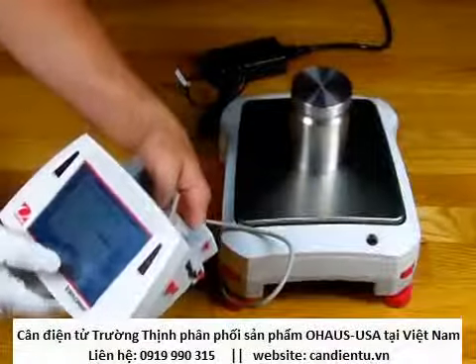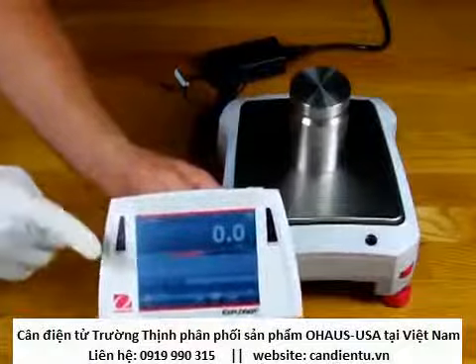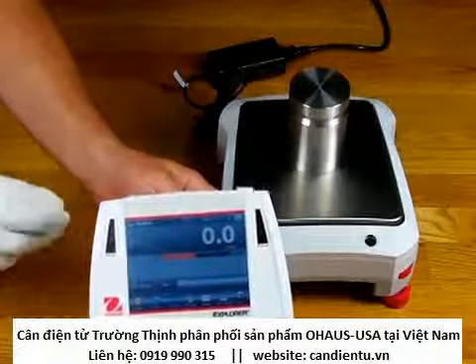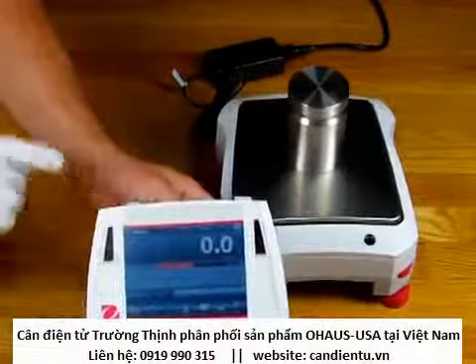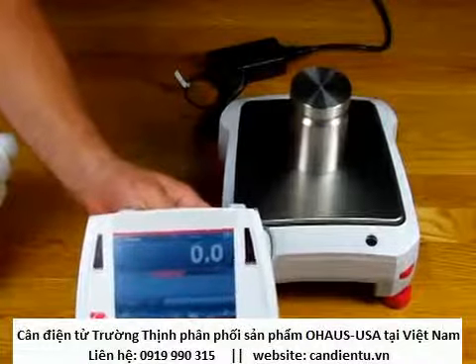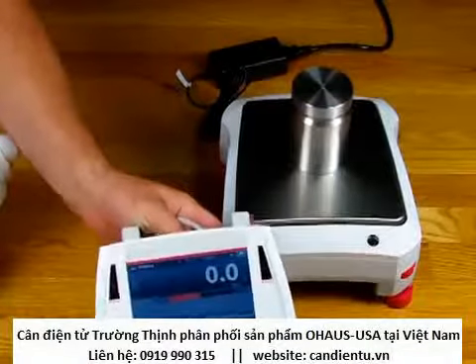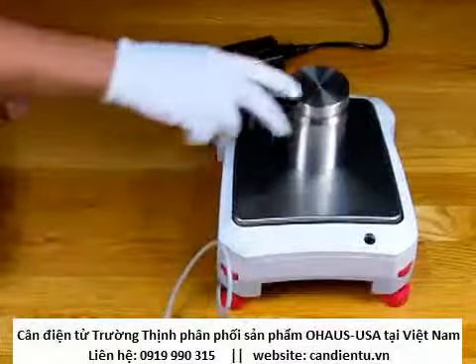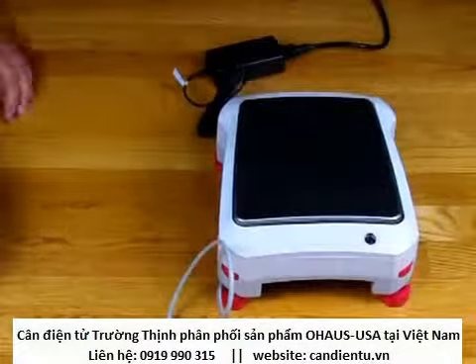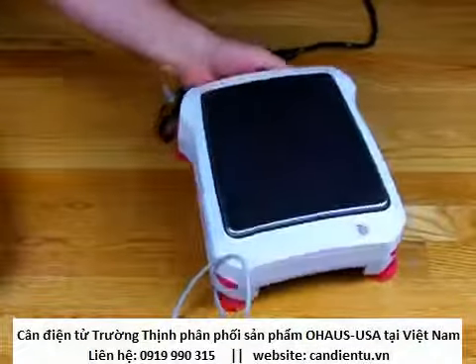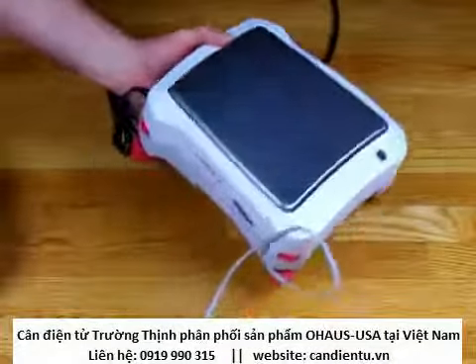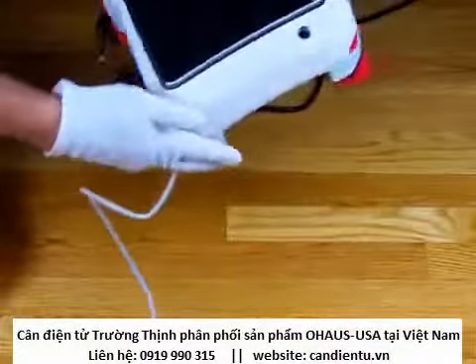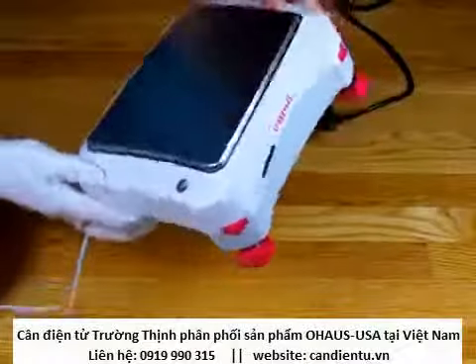We have two infrared sensors here, which allow you to tare out the balance, or you can have it so when you wave your hand over this sensor, it sends the weighing results via the RS-232 to a printer. The balance also has two sensors on the balance itself, located on one side and on the other side of the balance.